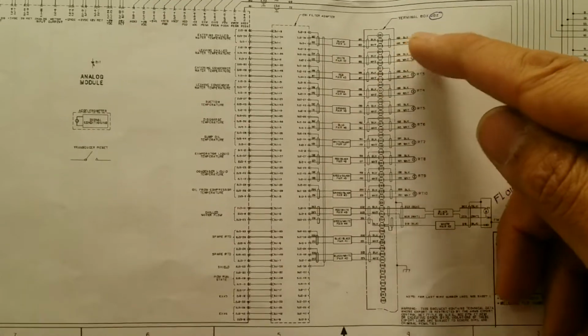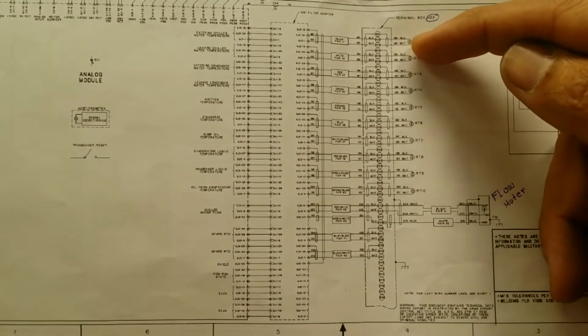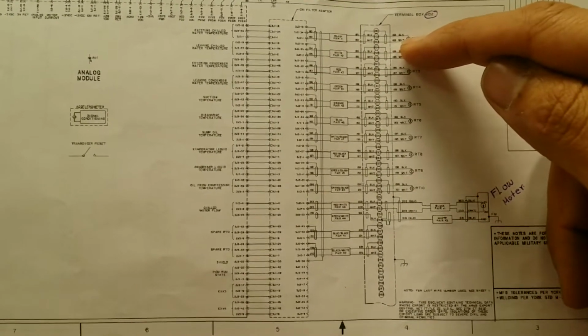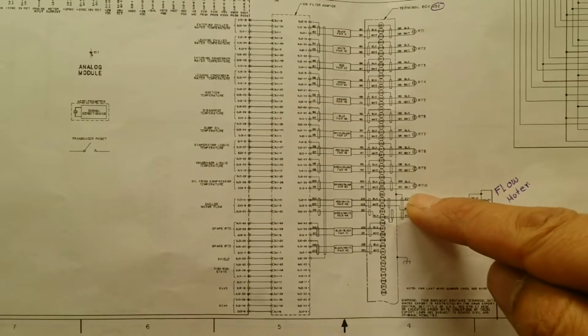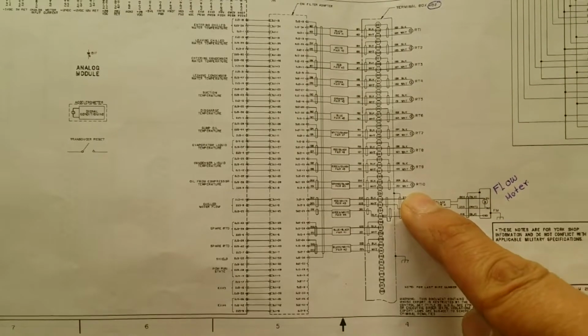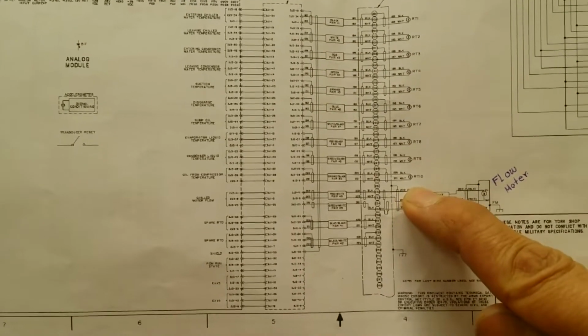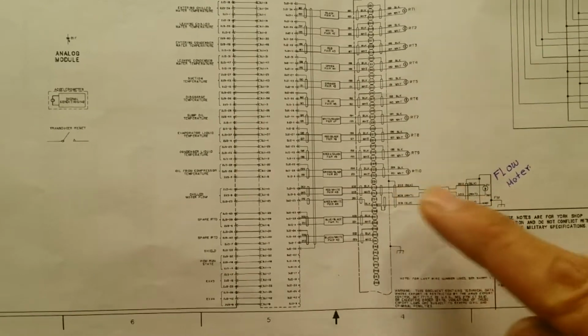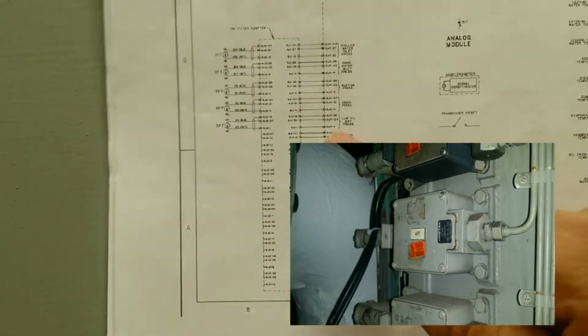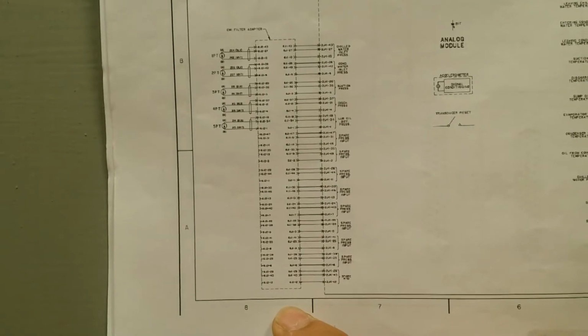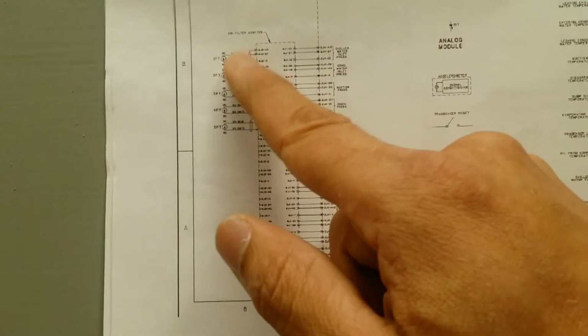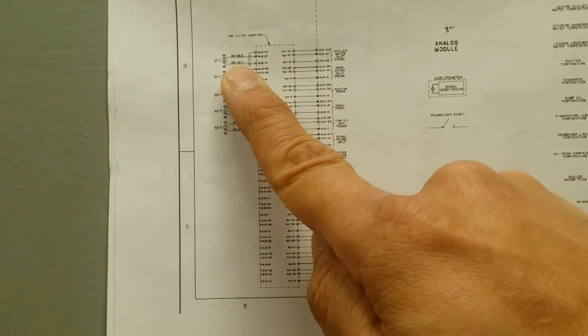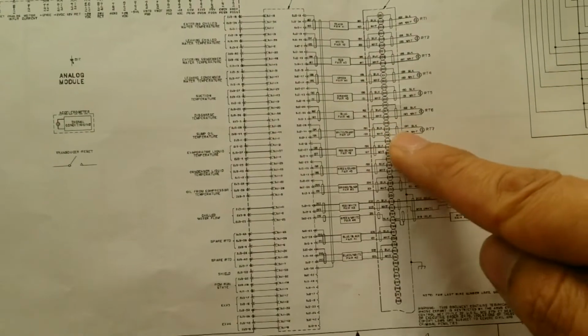Another thing that you can do from here is read the thermistors, which are actually variable resistors that are temperature sensors. Those are the RTs, 10 of them, and their resistance depends on the temperature they have, and you can actually read them with an ohm meter, so you can do a field test. I will show you what I mean by that in a moment. You can also read the flow meter to one side, to the left side, and here I have what is called the pressure transducer, 5 of them. Unfortunately, you don't have a terminal board to read all these pressure transducers, but you can actually read them on the transducers themselves. I will show you what I mean by that later. So let's see how you would read these.